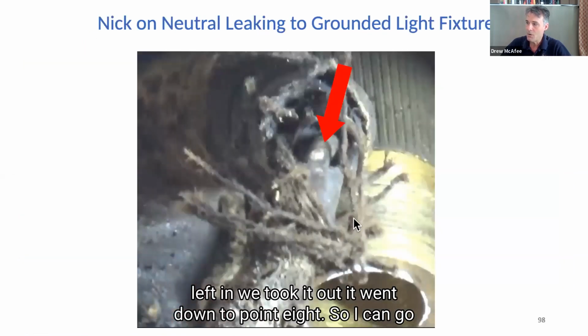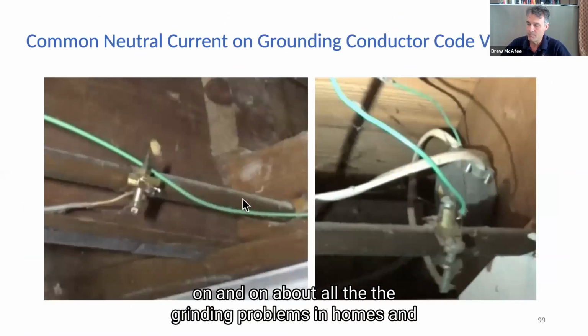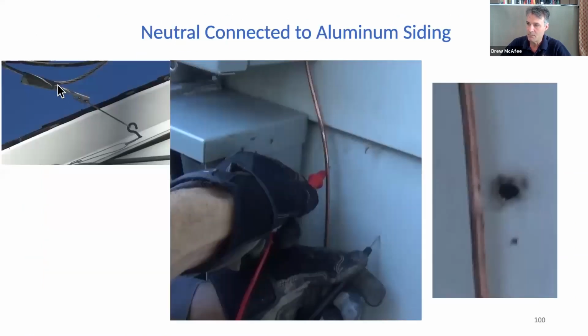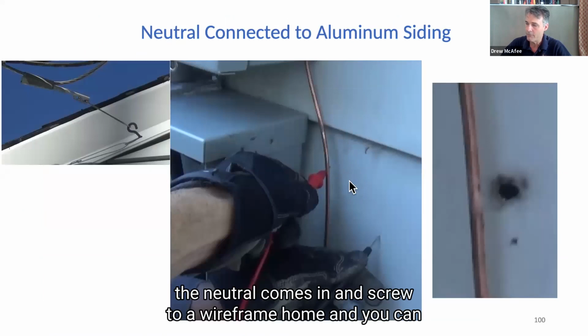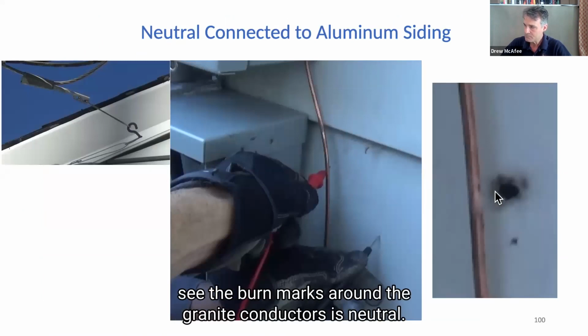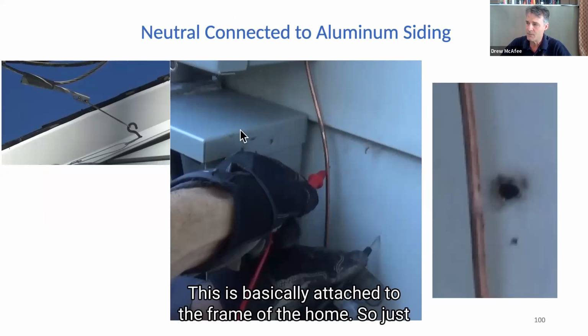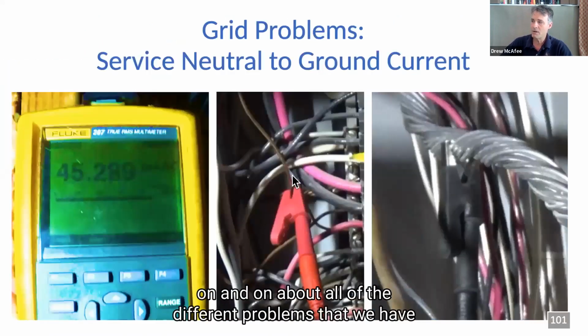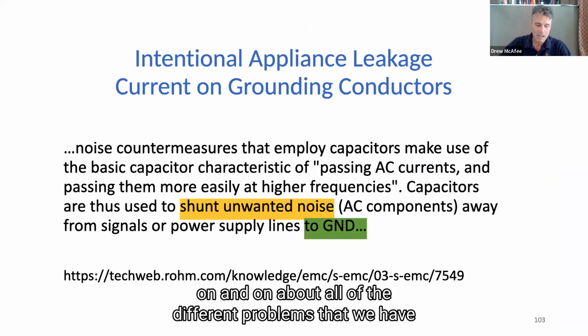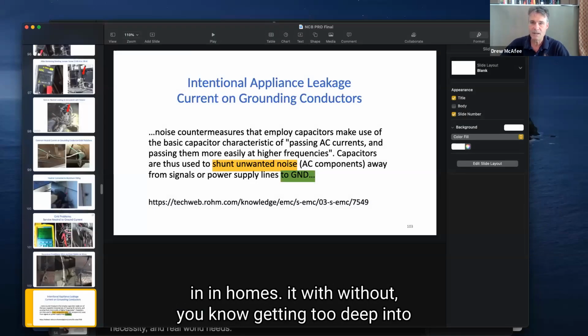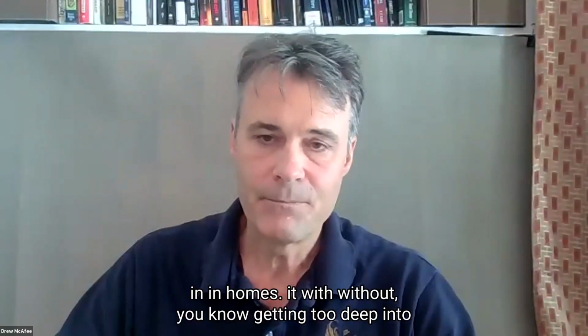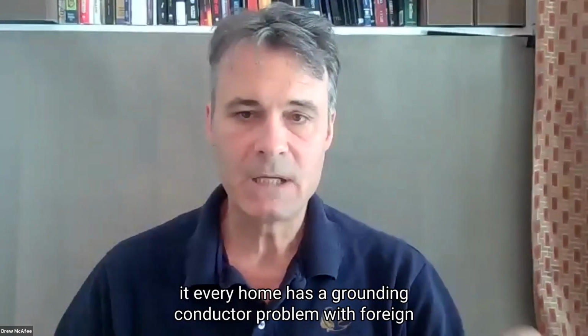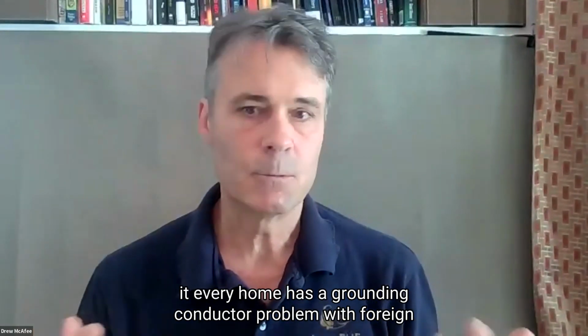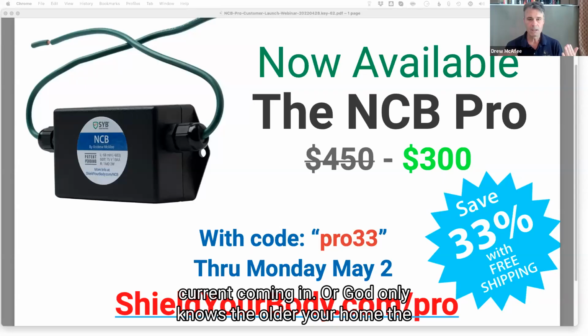I can go on and on about all the grounding problems in homes. Here the neutral comes in and is screwed to a wire frame home, and you can see burn marks around the grounding conductors. This neutral is basically attached to the frame of the home. So just on and on about all of the different problems we have in homes. Without getting too deep into it, every home has a grounding conductor problem with foreign current coming in, or God only knows.